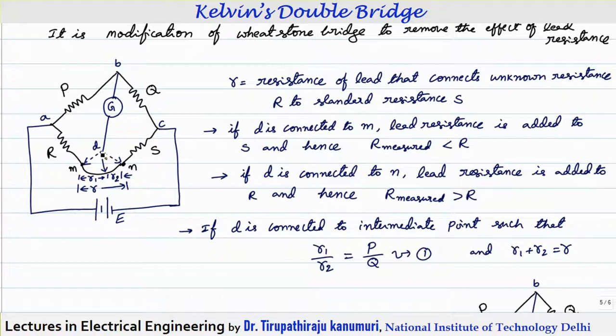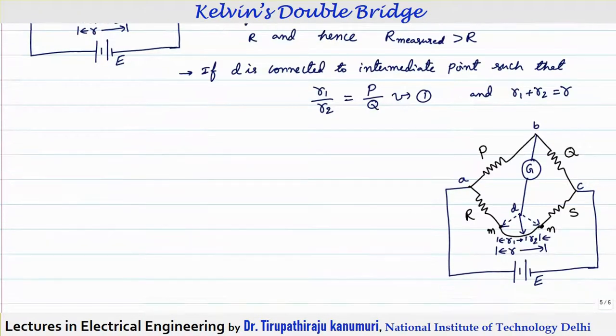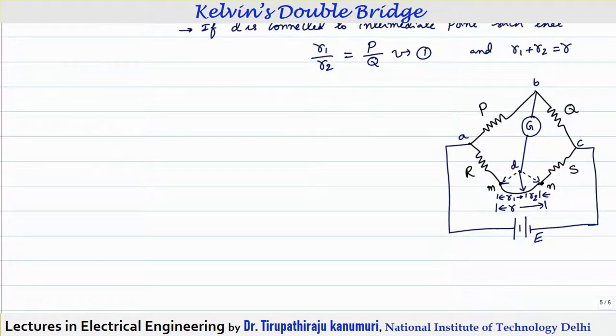In order to avoid the error, we have to connect somewhere in between this lead. Assume we have the flexibility to connect the lead on a bare conductor where we can adjust the sliding position. If the total lead resistance equals small r, then connecting at an intermediate point divides the total resistance r into two parts r1 and r2, where r1 + r2 = r. We locate this point such that r1/r2 = P/Q. Then the effect of lead resistance will be avoided.